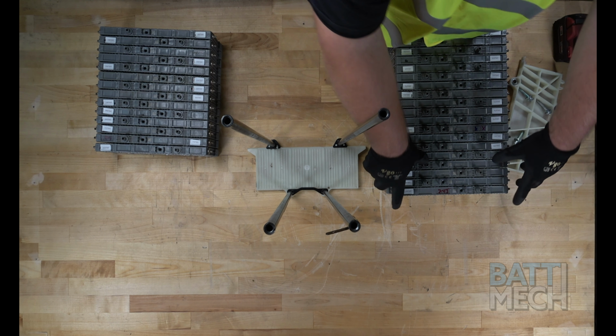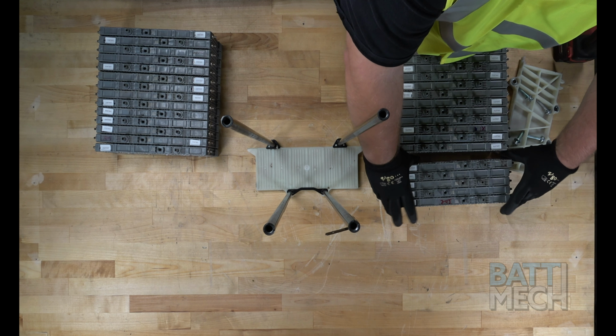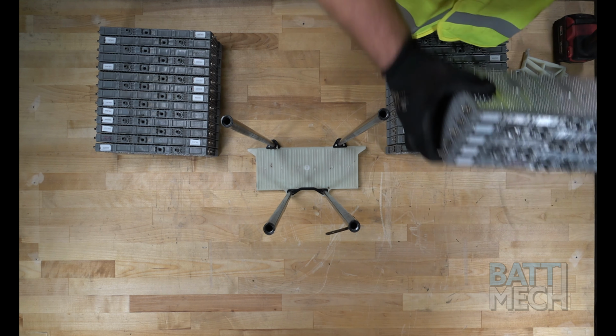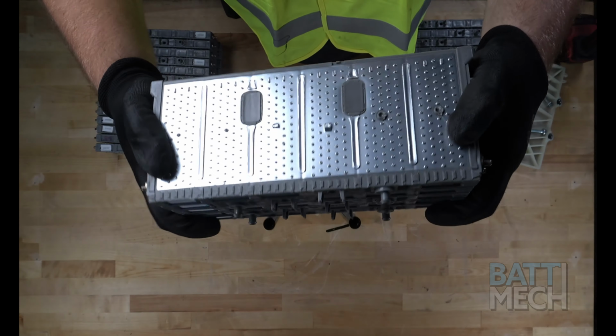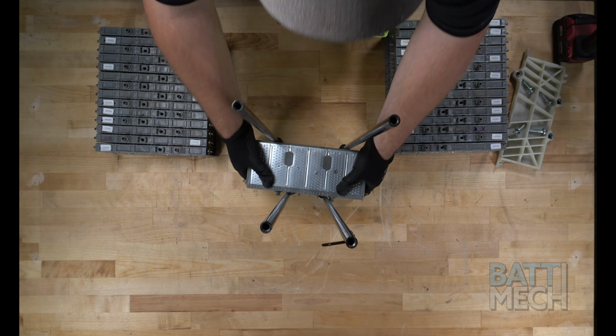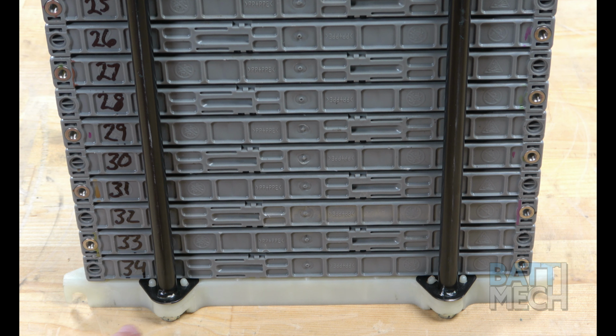Once your mech-tested BattMech batteries have been removed from the boxes they were shipped in, go ahead and stack them sequentially, from number 34 on the bottom up to number 1 at the top. Be sure the metal tabs are at the bottom or foot of the compression block before you assemble the battery modules into the compression block.